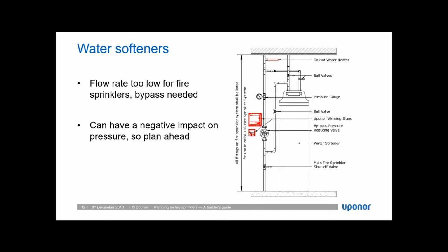Then when a sprinkler operates, the pressure in the system will drop significantly enough that the pressure at that valve will be low enough that water will begin to flow through there. It's important as well to pay attention to the valve being used as your bypass, because the water will be flowing directly through the valve when you have sprinkler operation.